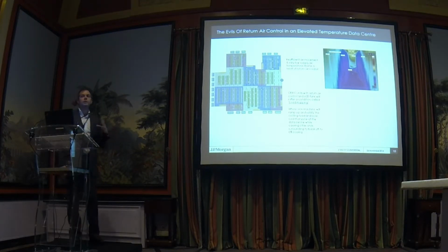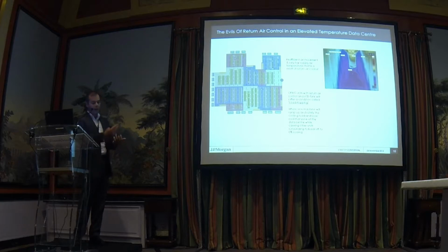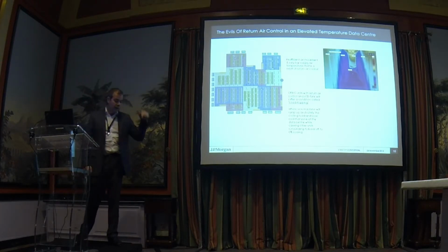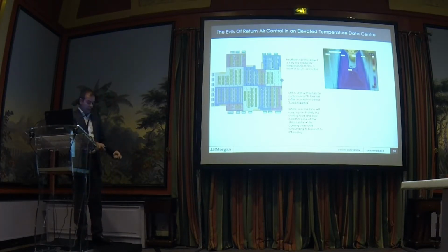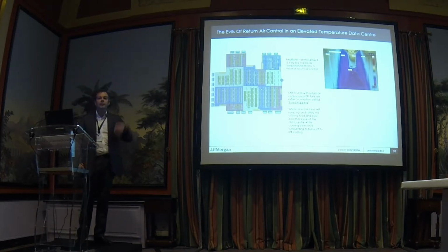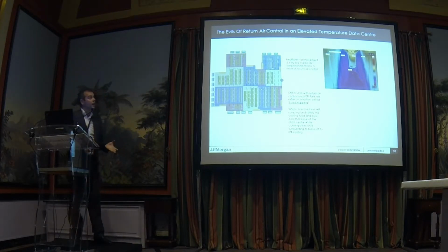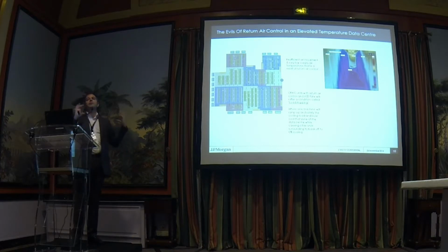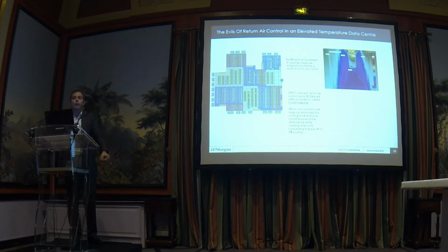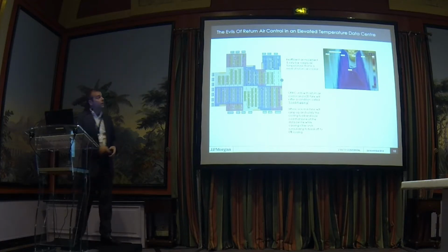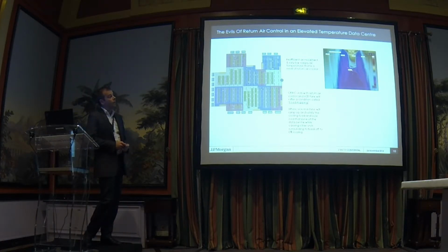When you have venturis under your floor where you've got high pressure air shooting out of the CRAC unit, and you've got a suction point, you've actually measured a couple of 100 litres of air a second being sucked back down into the floor, because the data center wasn't held at a global static pressure because of the easy openings the air could just shoot out of. Once you get a static pressure across your floor that's even, that venturi point will actually disappear on you. So after I'd gone around and shut down all the tiles, that purple strip went all the way through and even air coming up.